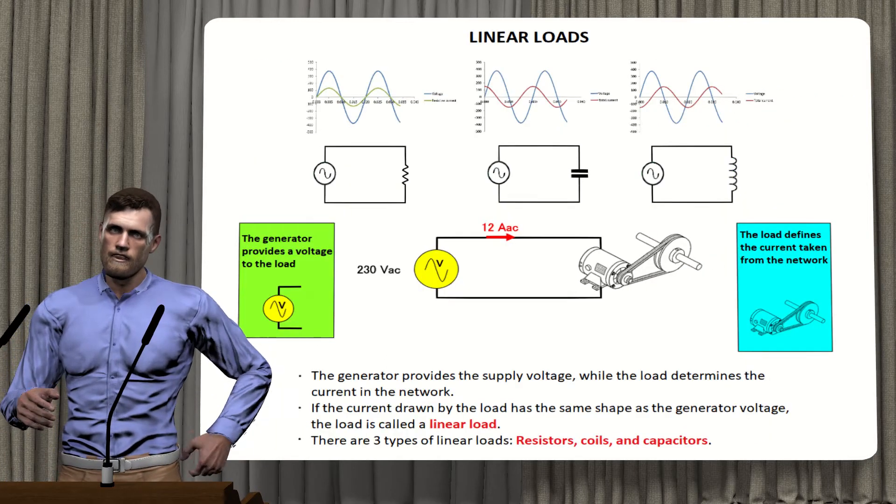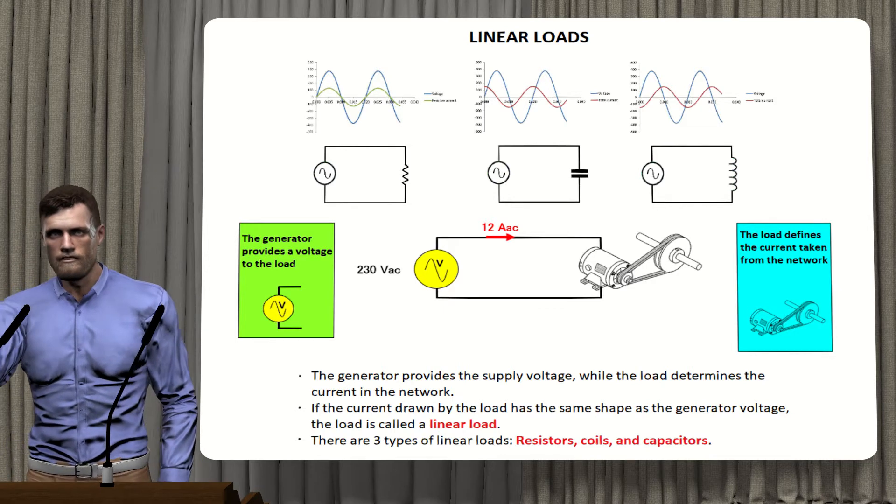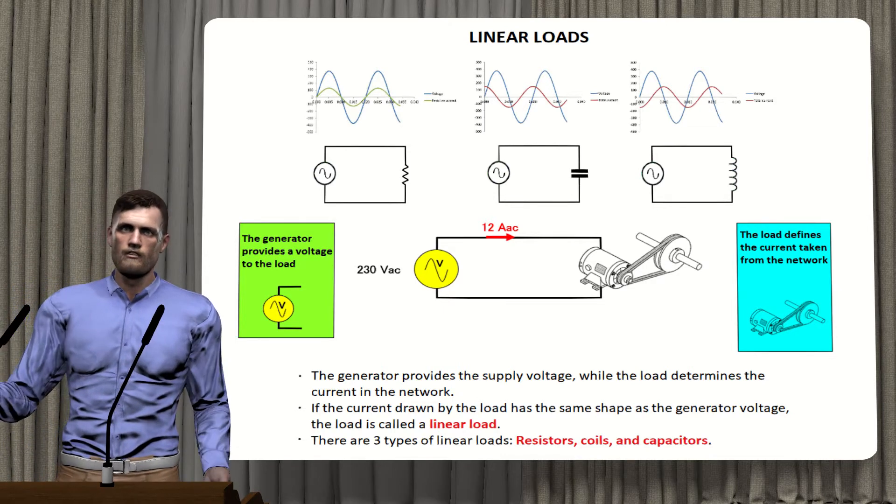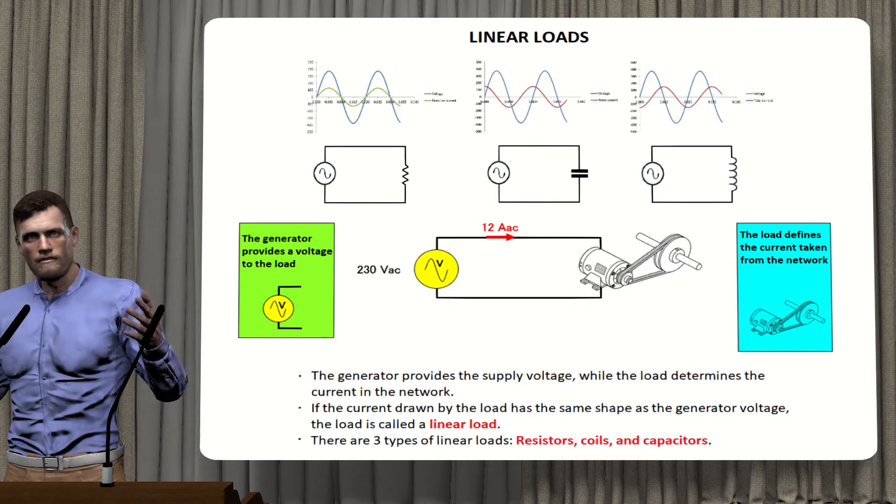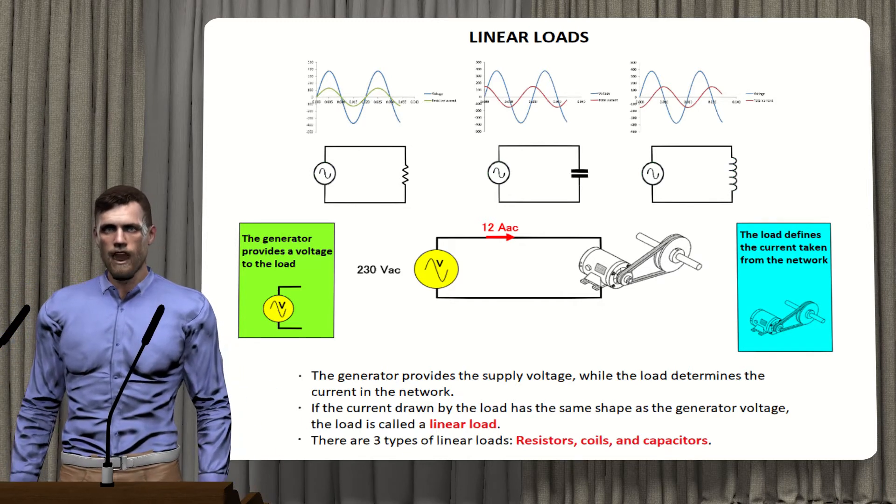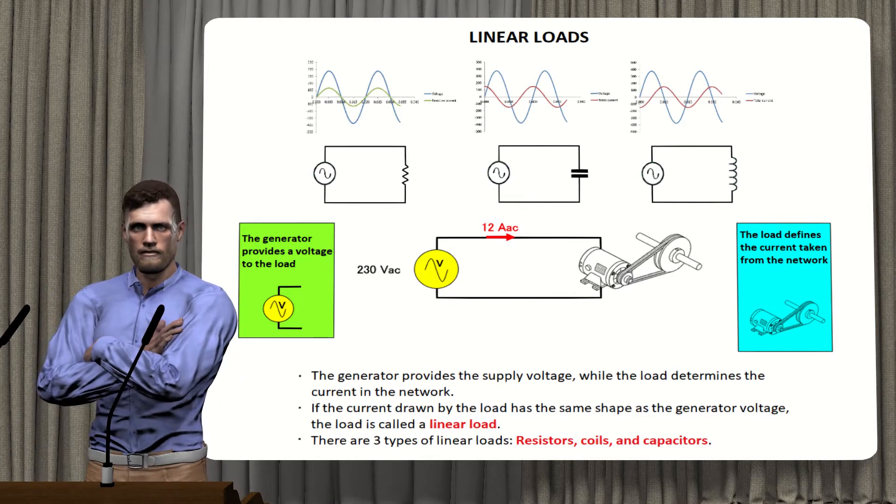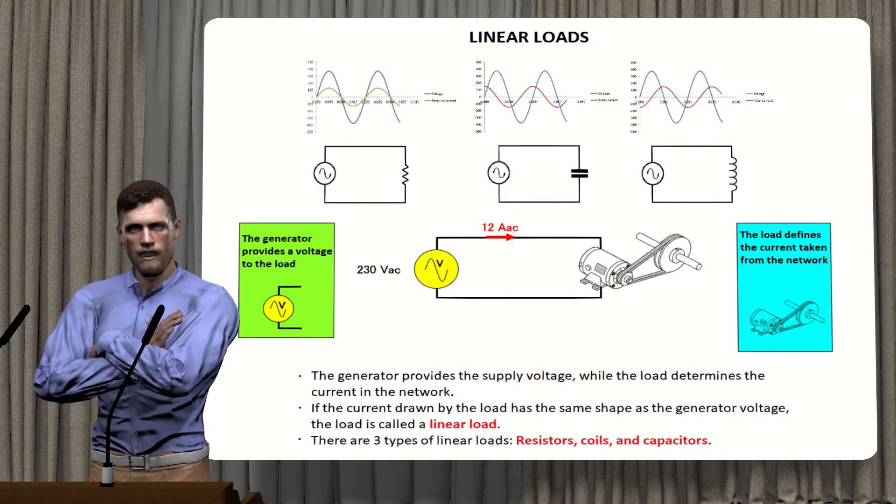The loads that are connected to the electrical network can be divided into linear loads and non-linear loads. Linear loads such as coils in motors, resistors and capacitors, when powered with a sinusoidal voltage waveform, give rise to sinusoidal currents, although there may be phase shifts between voltage and current giving rise to reactive powers.